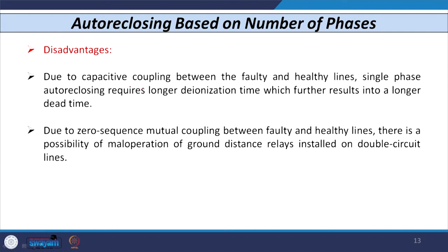The disadvantages of single phase auto reclosing include: due to capacitive coupling between faulty and healthy lines, single phase auto reclosing requires a longer deionization time, resulting in a longer dead time. Additionally, due to zero sequence mutual coupling between conductors, there is a possibility of mal-operation of the ground distance relay, particularly when used for double circuit lines where six conductors emanate from one bus.